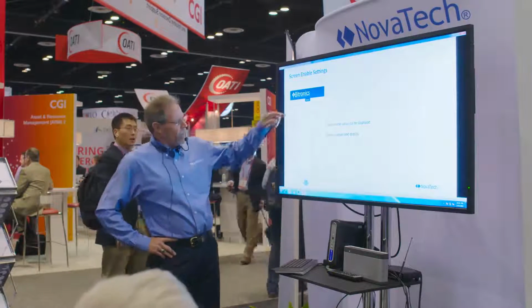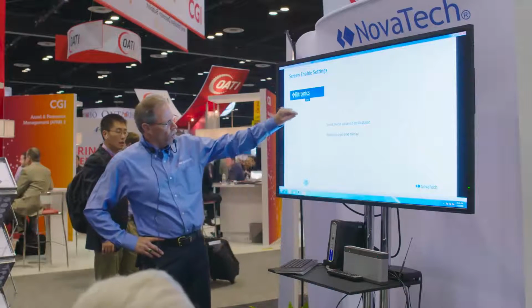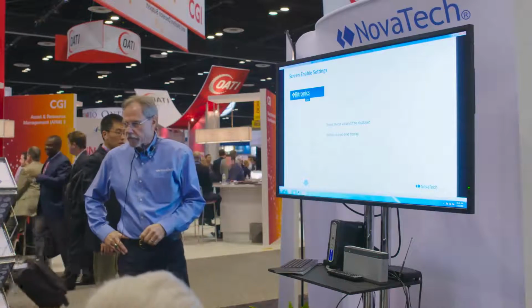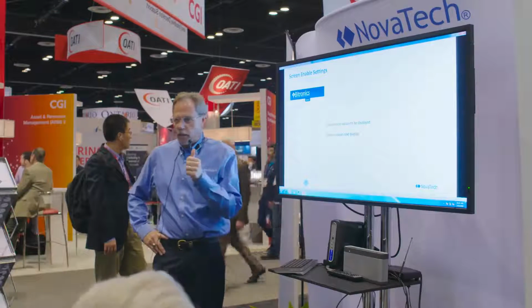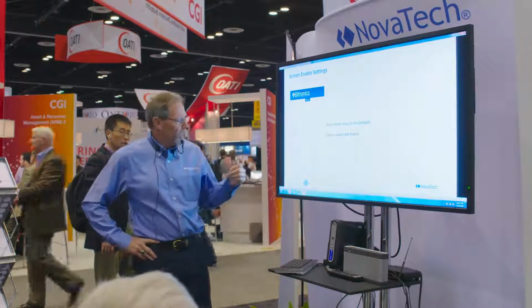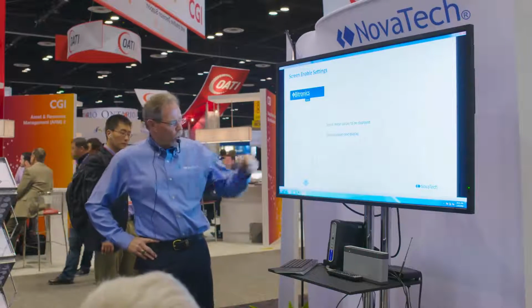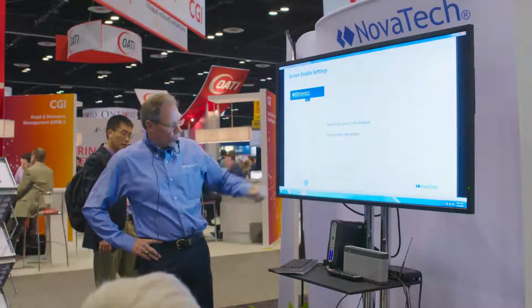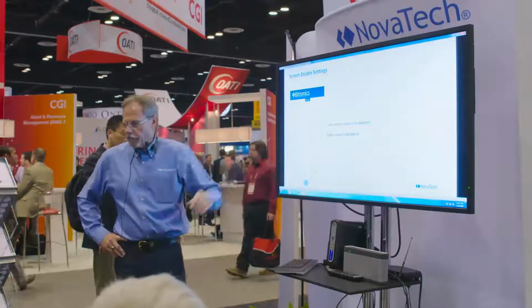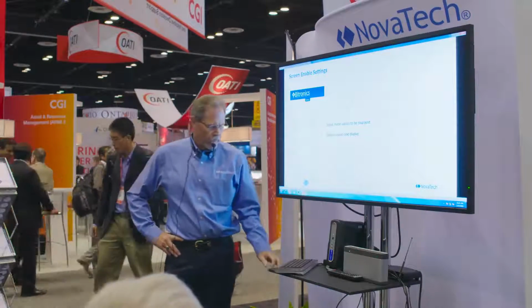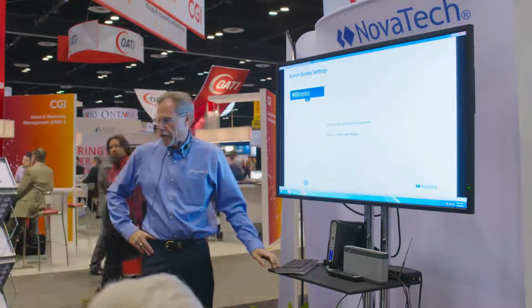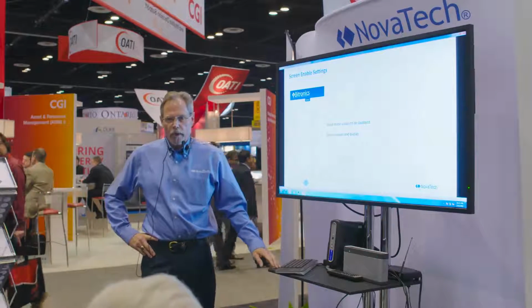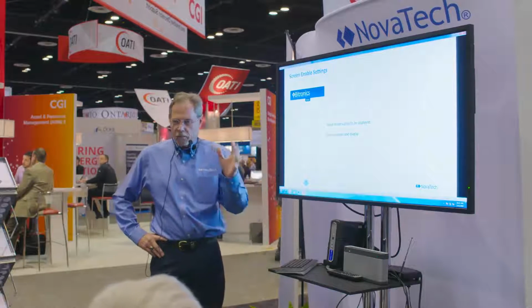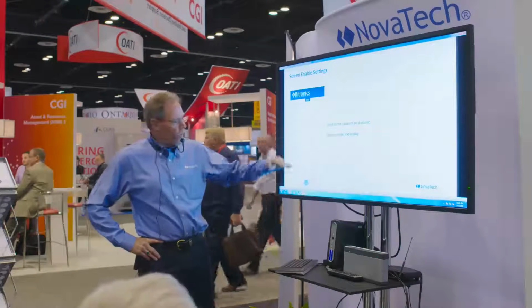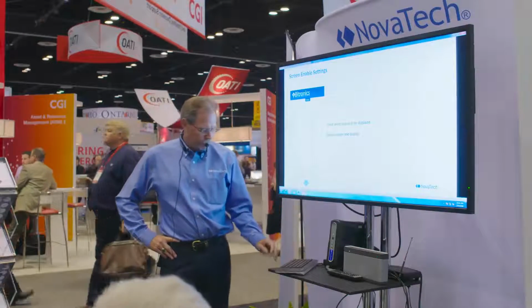For the display, I've got a checklist of the different quantities that I want that panel meter to display, either as I scroll through it manually, or if I put it in the auto scroll mode, those are the quantities that it's going to display for me. Out of the about 58 values that we've already defined for you, we also give you 10 user-defined values, so you can actually go in and write a custom display if any of those screens don't match what you want to see.